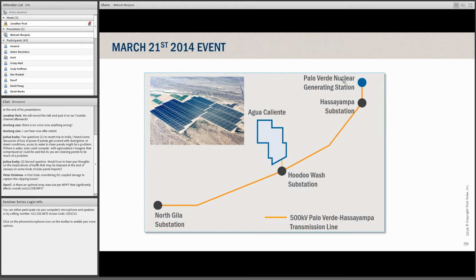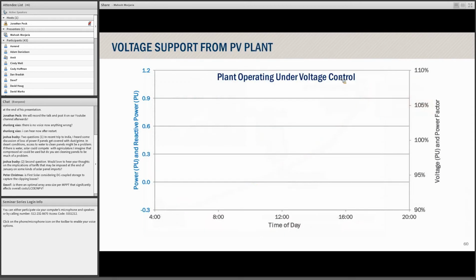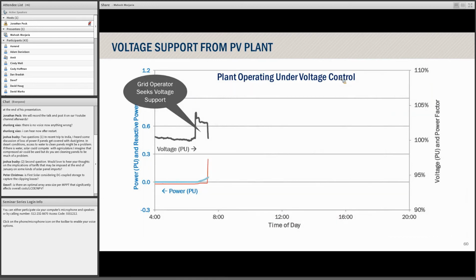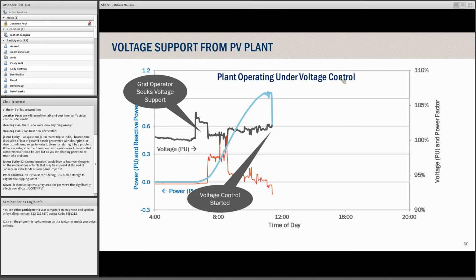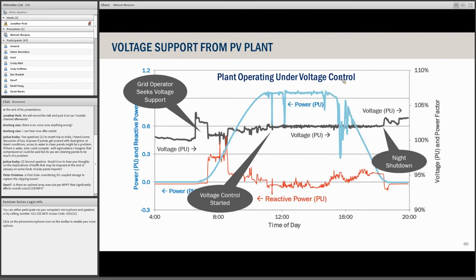Well, 3 years later, after the plant was commissioned, this particular transmission line went out of service, and the grid operator started noticing, see that black line? That's where, remember, previously the voltage was very stable. Here the voltage is fluctuating because that nuclear plant is no longer on that network. And so the grid operator said, hey, you guys were saying something about grid-friendly power plants. Can you see if you can control the voltage? And so you can see that black line, which is the voltage, it is being controlled, even though the power, which is the blue line, is changing.